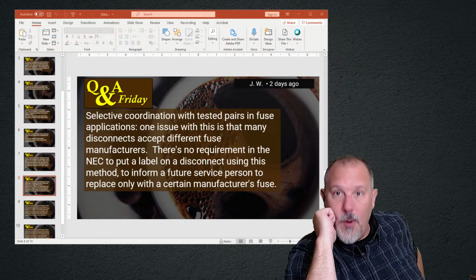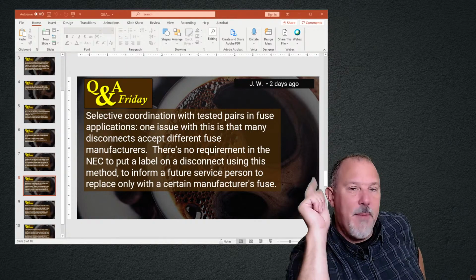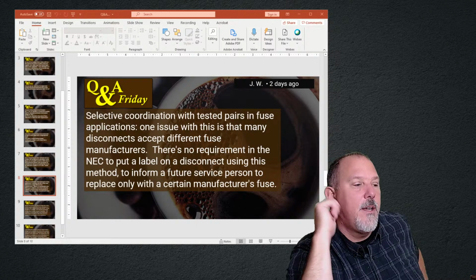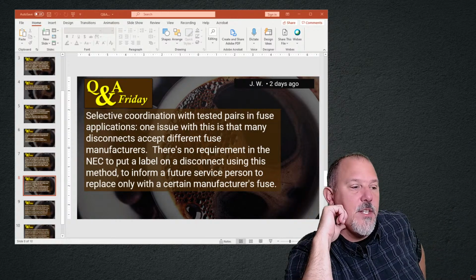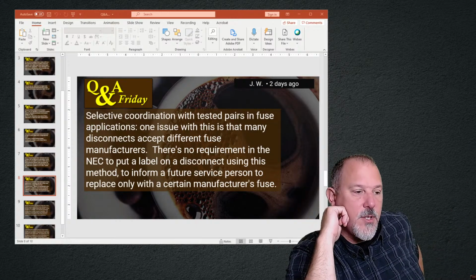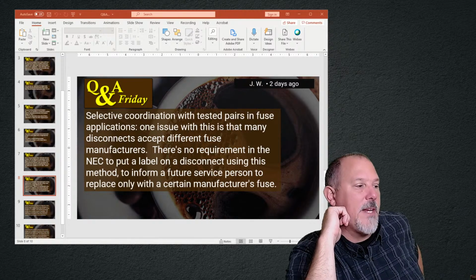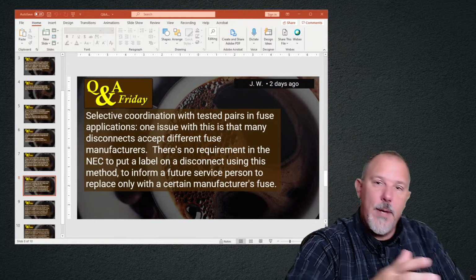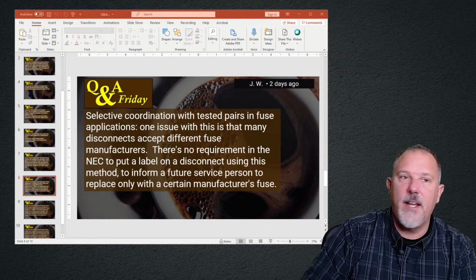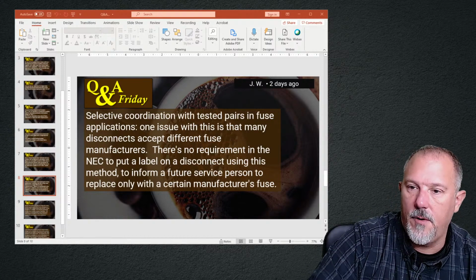And it was resolved, and the panel statement was the information referenced by the submitter is already available and required. 700.32 mandates that the, quote, selection shall be documented and made available to those authorized to design, install, inspect, maintain, and operate the system. So it is already required to be available. It's just not required to be marked on the equipment.